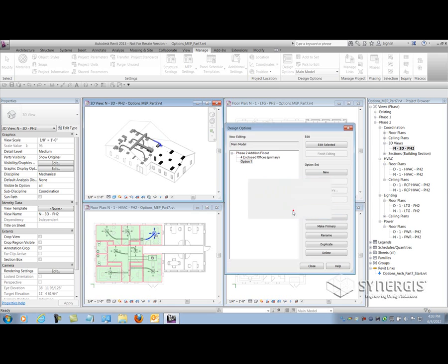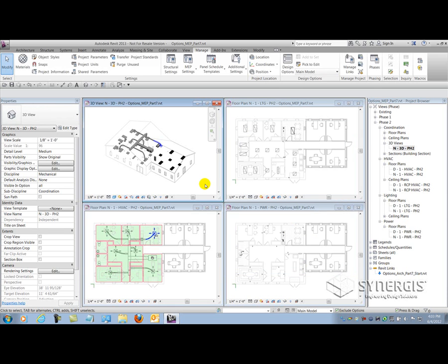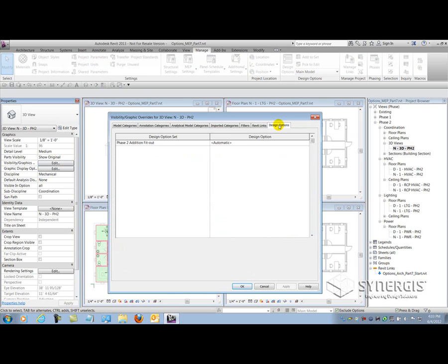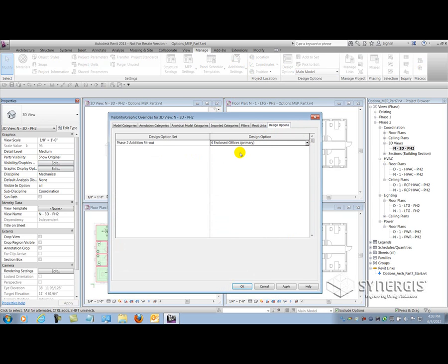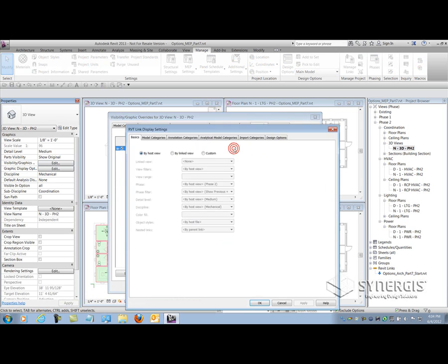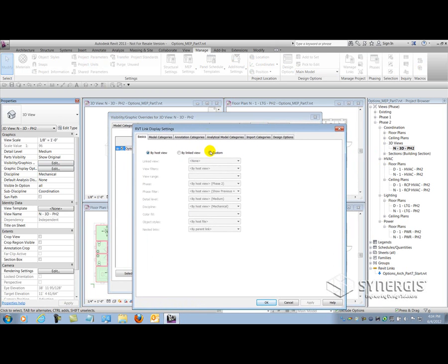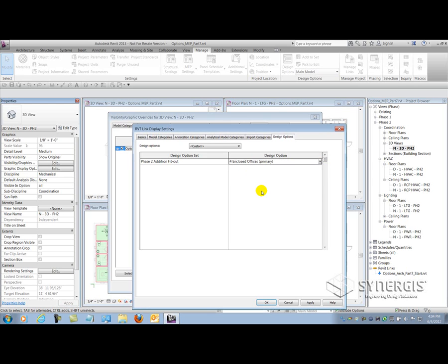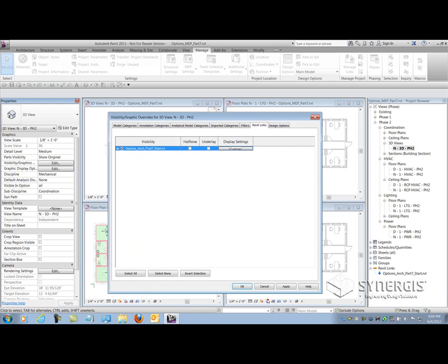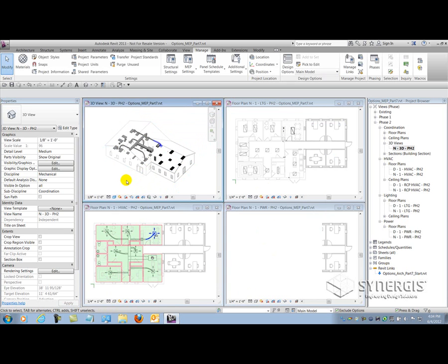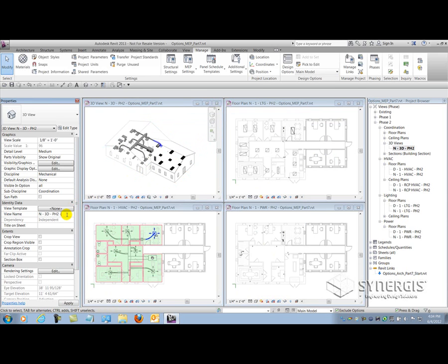With my design options set up now, I can focus on creating my views of each option. I'm going to go back into the visibility graphics dialog, go to design options now that I have them set up in my project, and specify that the primary option is visible in this particular view. Then I'll select the Revit links tab and go to the host settings of that particular link, set it to custom again, and specify the design option within the linked architectural file to match the one in my MEP file. When I OK my way out, I have a view dedicated to that particular option.